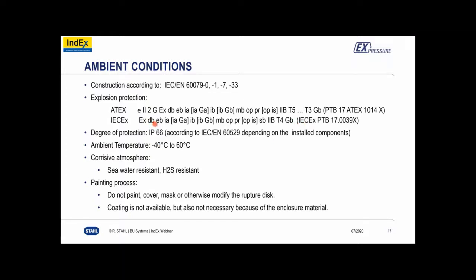So for the typical installation, you can be looking at many different protection techniques because you can have intrinsically safe barriers inside. You can have optical devices inside. So this entire combination of what the cabinet is rated for can be anywhere from EXDB SB or EXDB EB. There are many different combinations. So when they say that it is flexible, it is a very flexible cabinet that can be used for nearly any consideration. As mentioned, it is IP66. We're looking at -40 to +60. Because it's stainless steel, it's seawater resistant and H2S resistant. In the painting process, you do not paint, cover, mask, or otherwise modify the rupture disc. And coating is not available, but it is also not necessary because it is stainless 316.